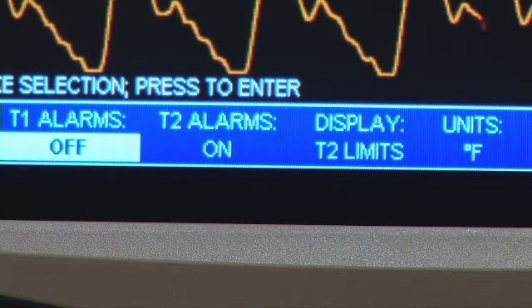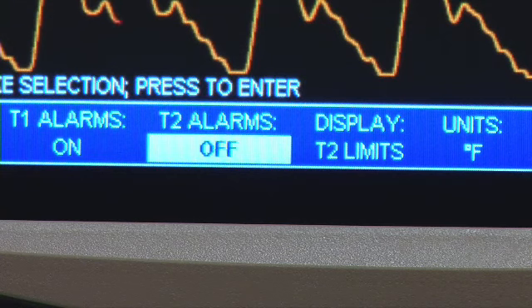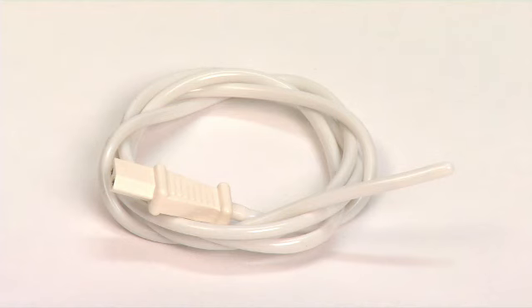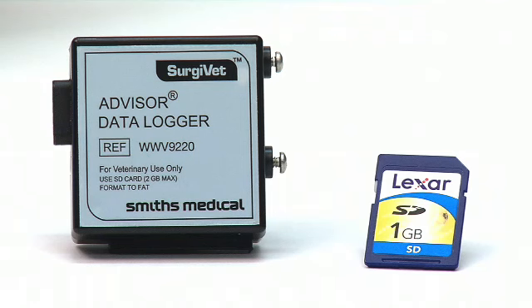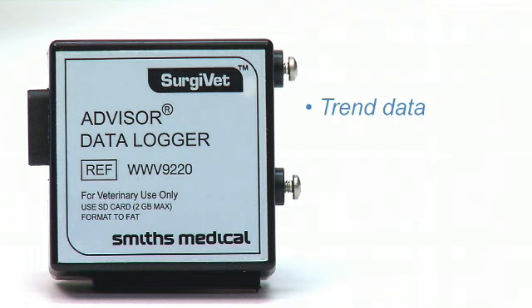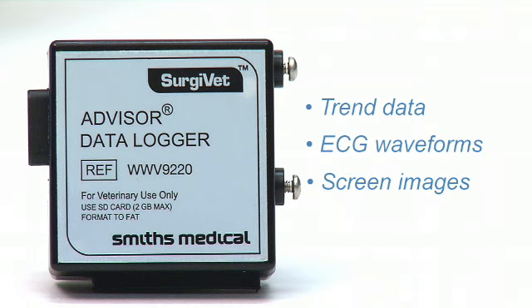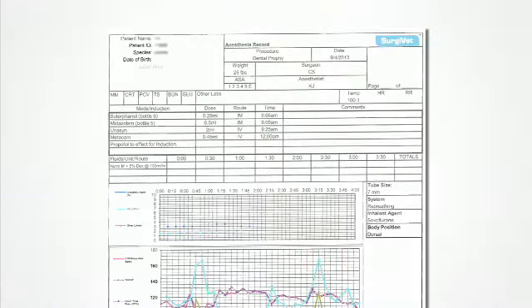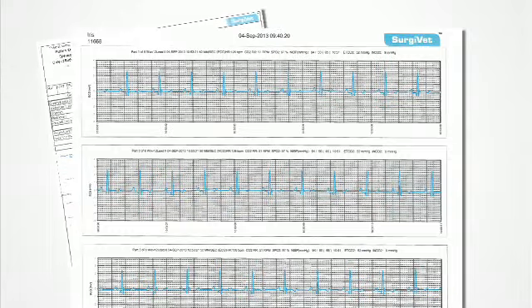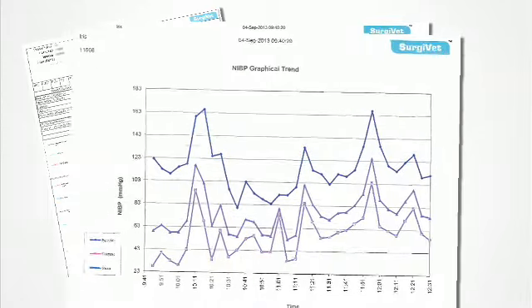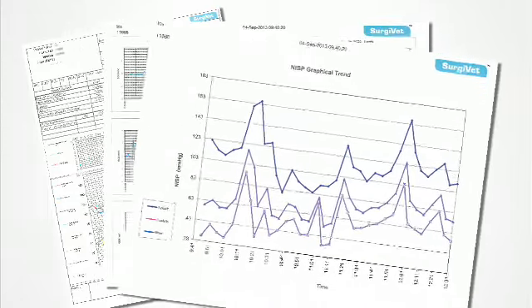Optional two temperature channels can be adjusted for both Fahrenheit and Celsius, and can be used for various measuring sites such as esophageal or rectal. The Data Logger is an optional hardware accessory that attaches to the Advisor Monitor to record trend data, ECG waveforms, and screen images. The information is captured onto an SD card and uploads using the Data Logger software on your PC. This saved information is then displayed in a basic or detailed anesthesia record, and can be printed off or saved into a paperless patient record.